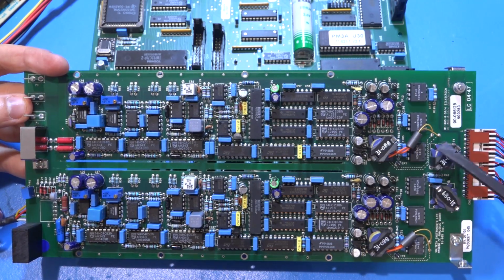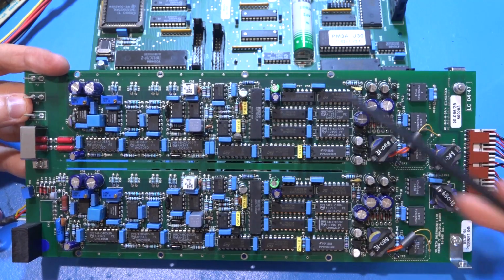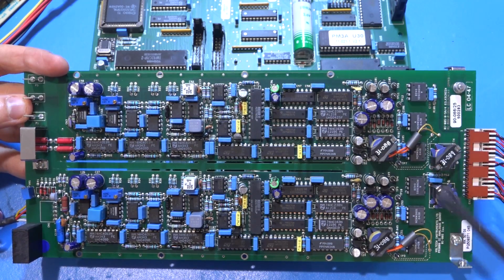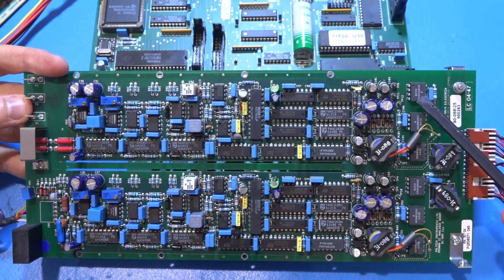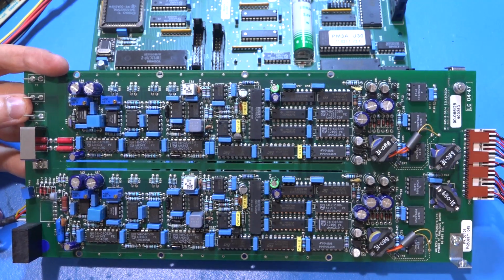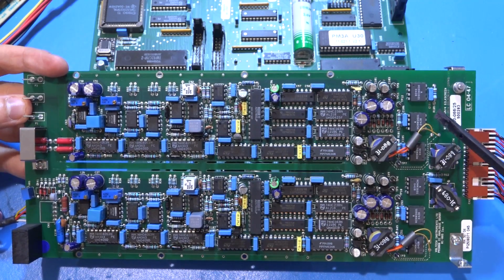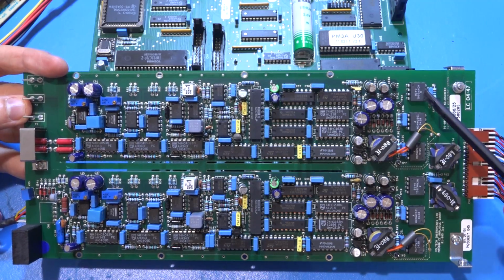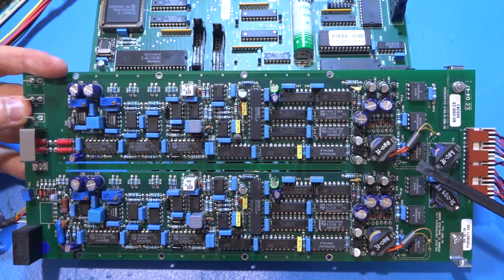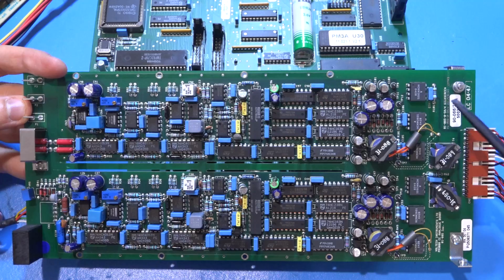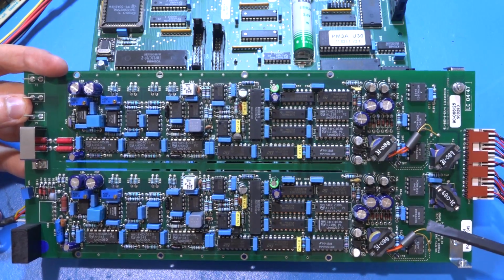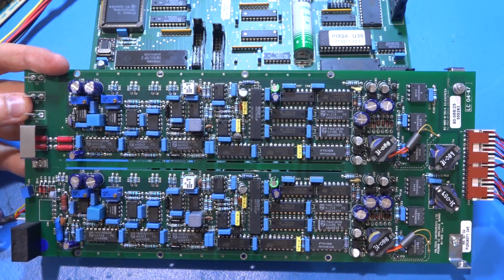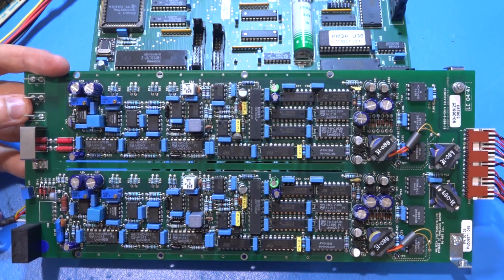They do galvanic isolation using pulse transformers to send the data over. And then there is a series of Broadcom opto-isolators. These are gallium arsenide phosphide photo generation, or LEDs inside with photodetectors on the other side. And that creates isolation, nothing unusual. These are designed specifically for digital I/O replacements across two different power supply domains. So they are basically sending data this way and this way using the combination of galvanic and optical isolation, as we suspected when we were looking at the architecture from before.